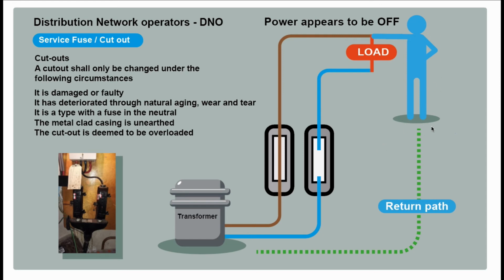And this is why you always need to carry out your safe isolation and test everything all the time. Test for dead all the time. You've got to test line to earth, neutral to earth. You always test. Because in this situation the line is still powered up, still energized. It's just not returning back on the neutral. But if you touch that line wire, you become that neutral. You become that return path, the earth path, back to the transformer. So you could have this load going through you. That's why a fuse neutral is very dangerous, because of the potential that you actually become the return path back to the transformer. So good care needs to be taken, and as always, safe isolation and making sure that every conductor is dead before you start doing any investigation.